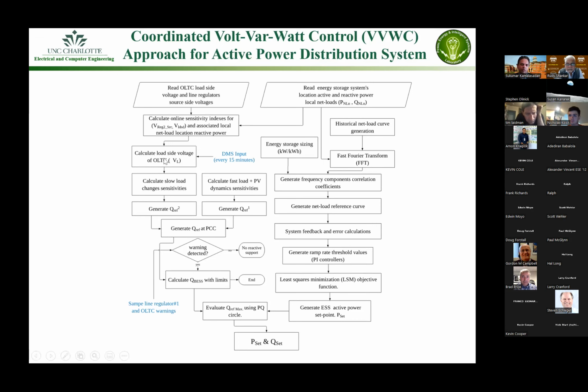We get a DMS output with the voltage-related regulators, capacitors, and obviously OLTCs. With that, you look at the sensitivity of the slow-changing load, the dynamically fast-changing load, and the PVs, and generate two reactive power references, one based on each of those time scales or sensitivities.